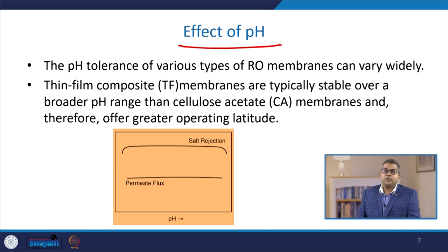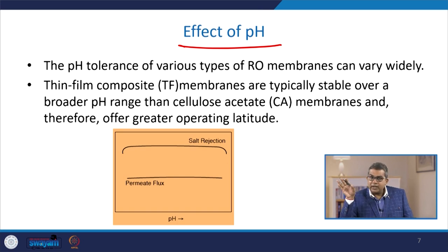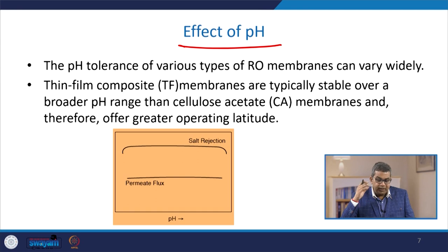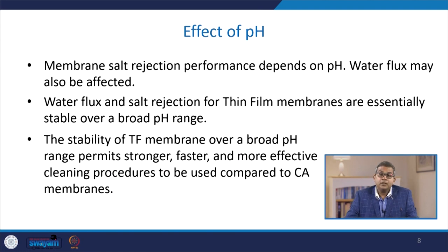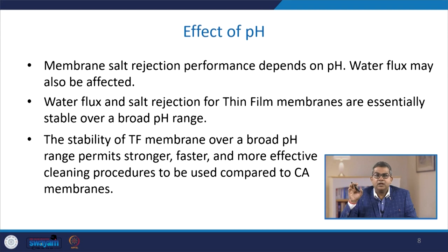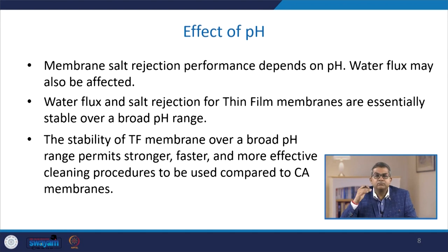Regarding the effect of pH, the pH tolerance of various types of reverse osmosis membranes can vary widely. Thin film composite membranes are typically stable over a broader pH range than cellulose acetate (CA) membranes, therefore offering greater operating latitude. The membrane salt rejection performance depends on pH, and water flux may also be affected. The water flux and salt rejection for thin film membranes are essentially stable over a broad pH range. This stability permits stronger, faster, and more effective cleaning procedures compared to cellulose acetate membranes.